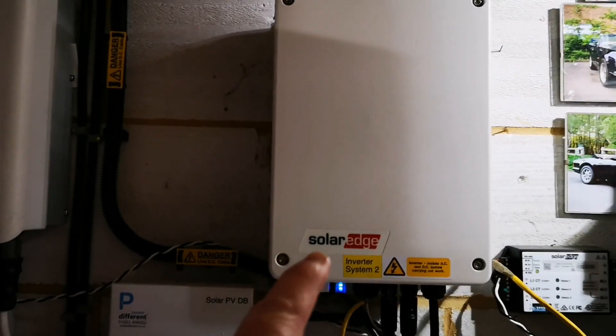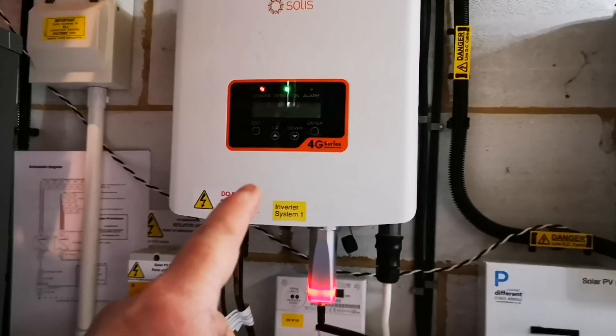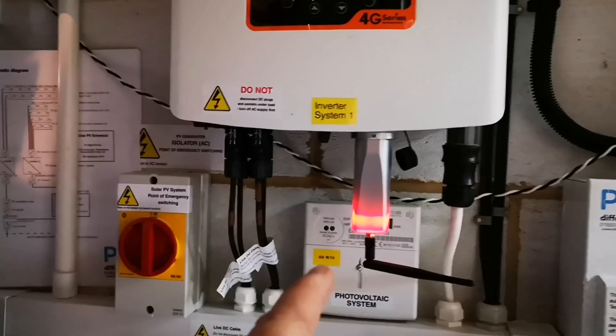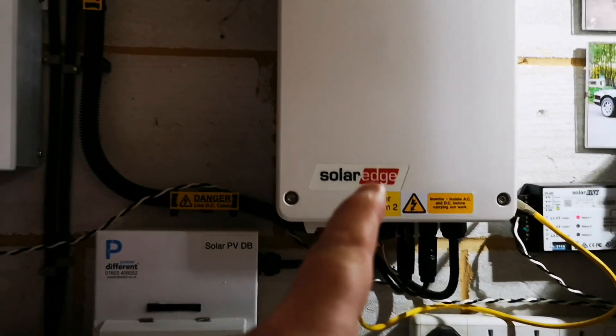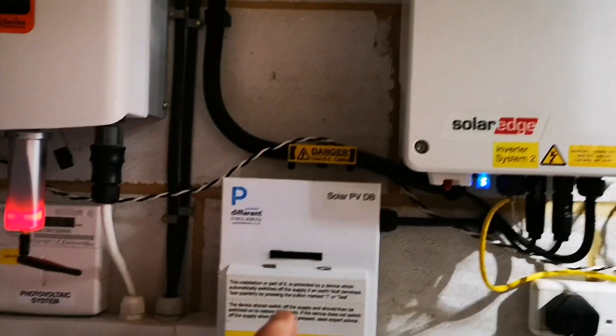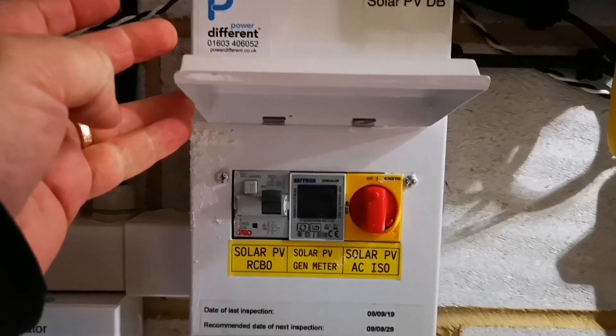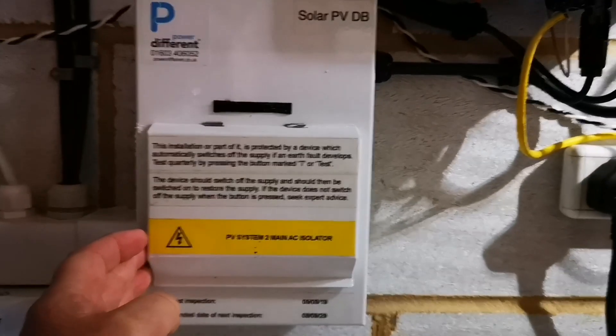We've got a SolarEdge inverter connected to eight panels on the roof. We've got a Solis inverter connected to 14 panels on the roof. They're completely separate. The Solis comes to a meter which is for my FIT payments, and because of the FIT payments this SolarEdge inverter comes into a separate box with a separate meter and a separate counter. So the two are isolated so that I'm doing the right thing by the FIT payments.